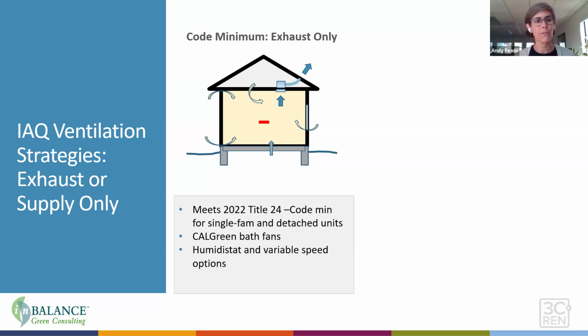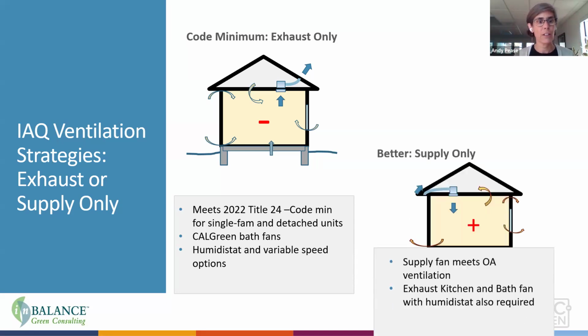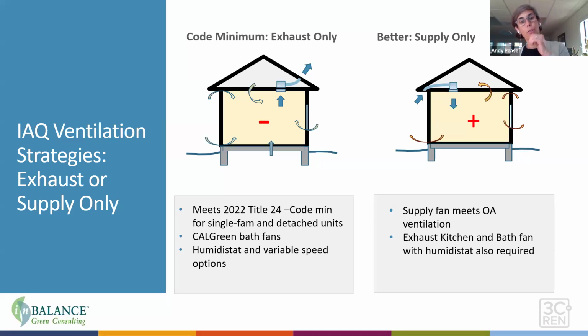Code minimum can be met with exhaust only, like a bathroom fan exhausting at a high level when there's humidity, but otherwise running at a low level or cycling on and off to provide continuous code-minimum air changes. You can do the same thing in reverse with a direct supply pushing air in. Either way, you're relying on the leakiness of the house. Supply-only is a bit better because you can control where the air comes from, versus exhaust-only, which might pull air from the crawl space, garage, or other areas not built as well.